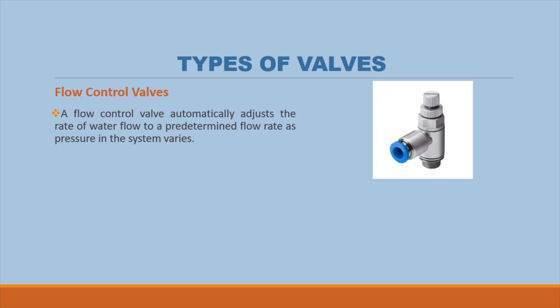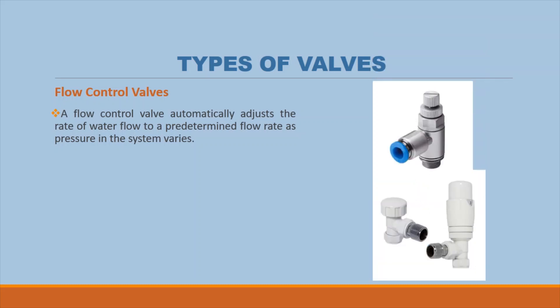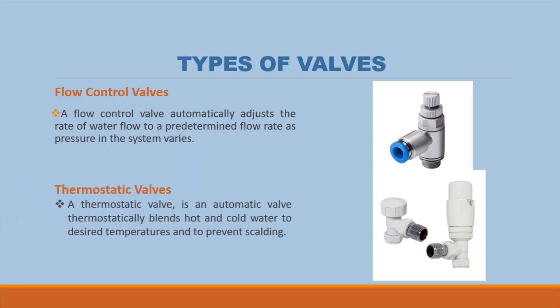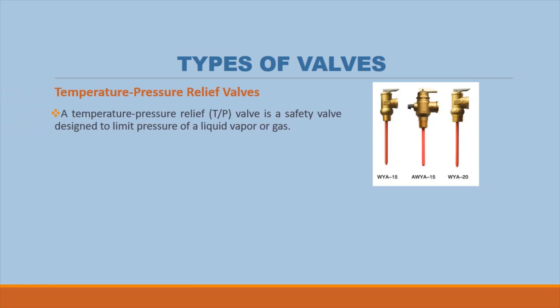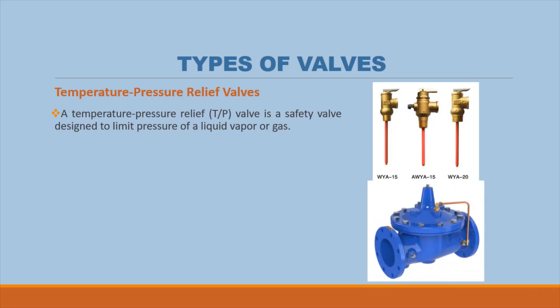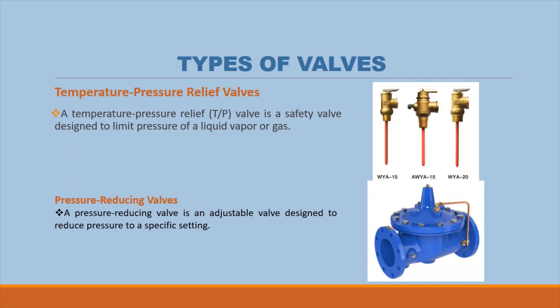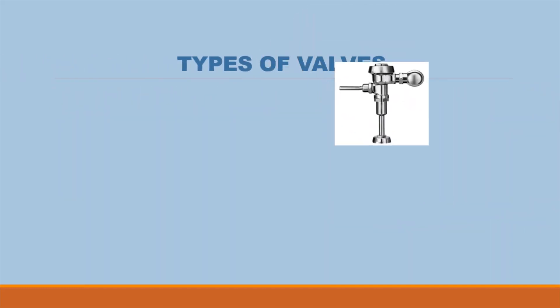A flow control valve automatically adjusts the rate of water flow to a predetermined flow rate as pressure in the system varies. A thermostatic valve, frequently called a tempering valve or mixing valve, is an automatic valve that thermostatically blends hot and cold water to a desired temperature to prevent scalding. A temperature pressure relief valve is a safety valve designed to limit pressure of a liquid, vapor, or gas.